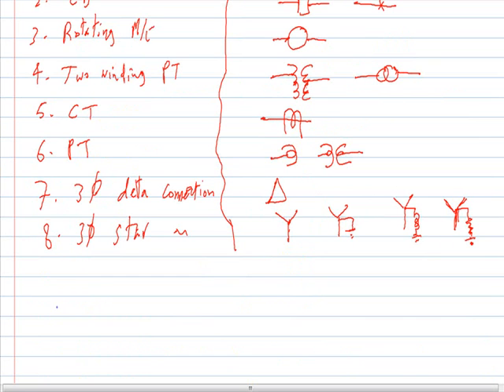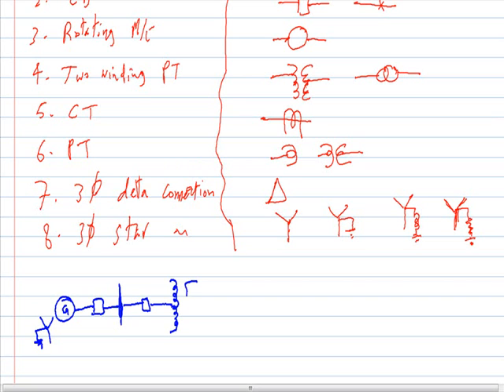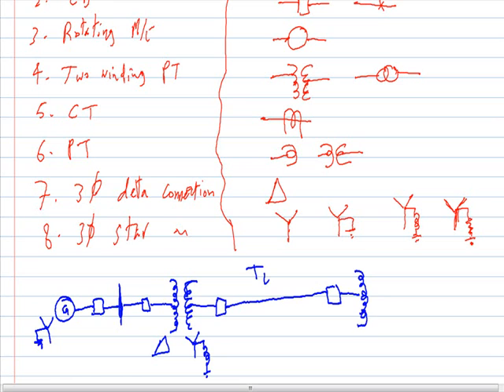The use of one-line diagram symbols is as follows: we have an electric generator — we add a circle and the letter G. If the primary is star-connected and solidly grounded, it has a circuit breaker. After the circuit breaker there is a bus bar. From the bus bar we have another circuit breaker connected to a transformer. From the transformer — a delta-Y transformer with the neutral grounded through a reactance — then another circuit breaker, then the transmission line, then another breaker.